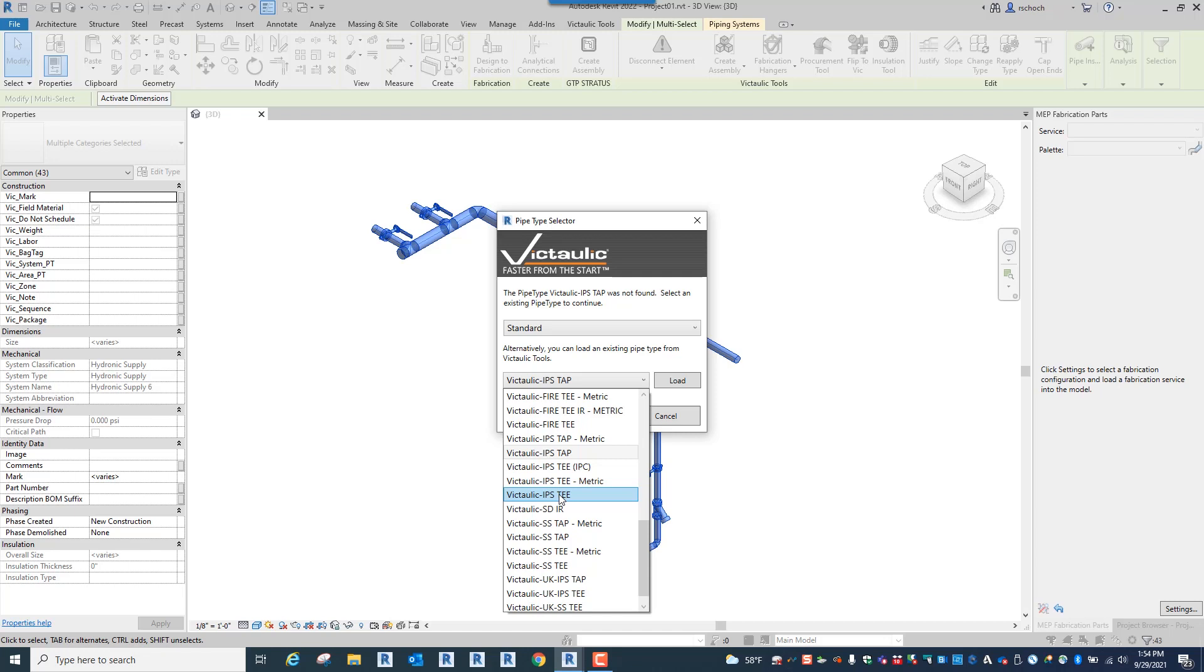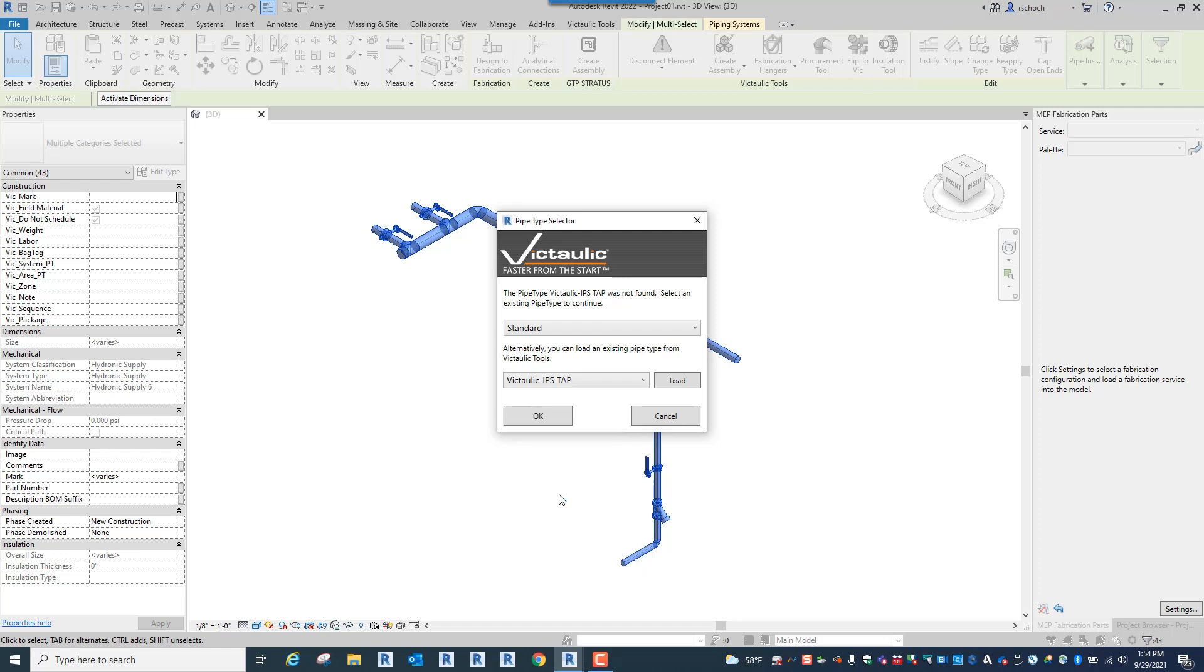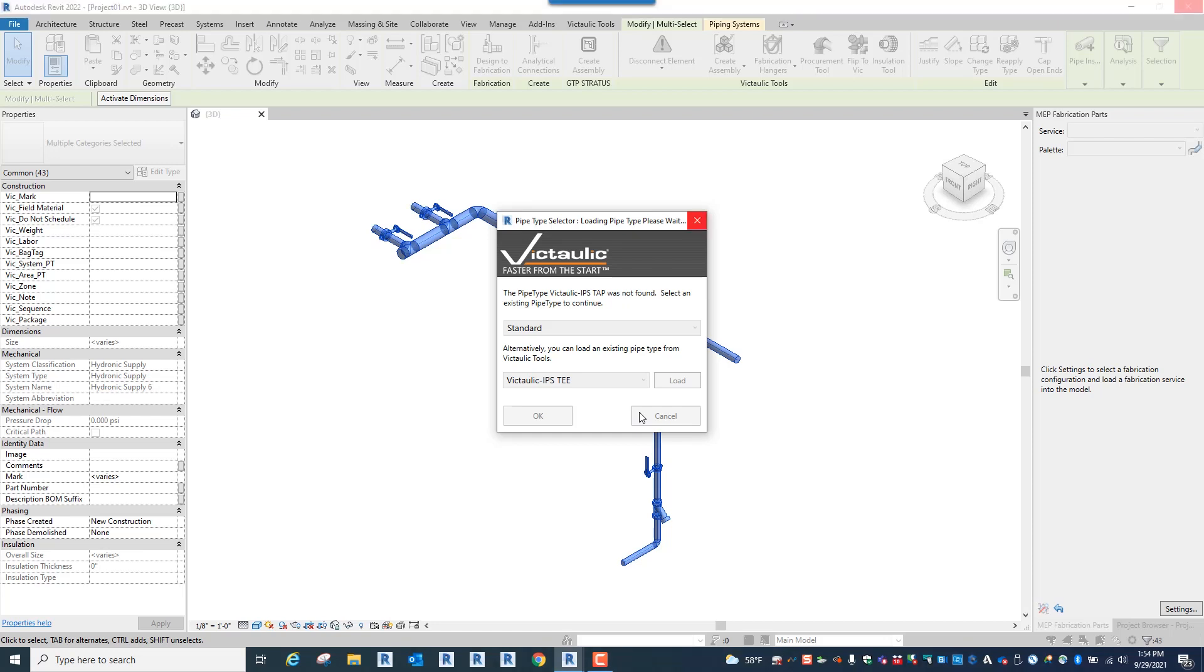For Revit, Revit has an issue in the way you route that if you want to tap coming off a branch or a tee, there's no way to create a single pipe type which is similar to a specification in Revit to route either tees or taps based on size. You have to select the tee or tap pipe type as you do this, and that's the main reason why you'll see in this drop down here that we have our pipe types broken down via tee versus tap. Just know that what you typically want to do is if you're doing a carbon steel system you're going to want to load the Victaulic IPS TAP and I'll click load. You'll notice that this load takes a few moments so what it's doing is it's programmatically building that pipe type in Revit.